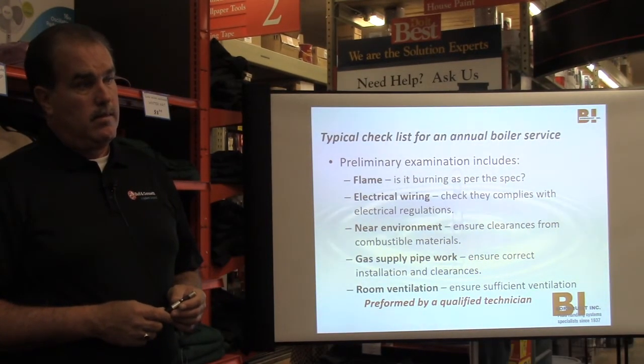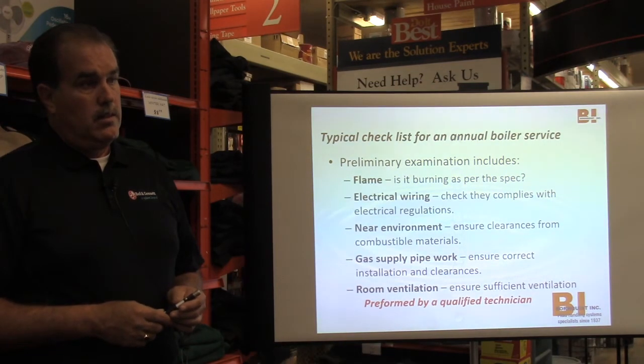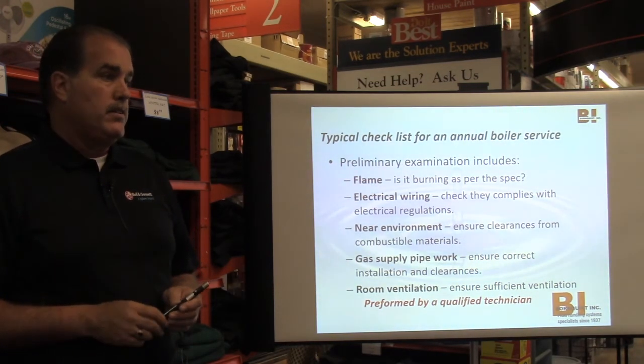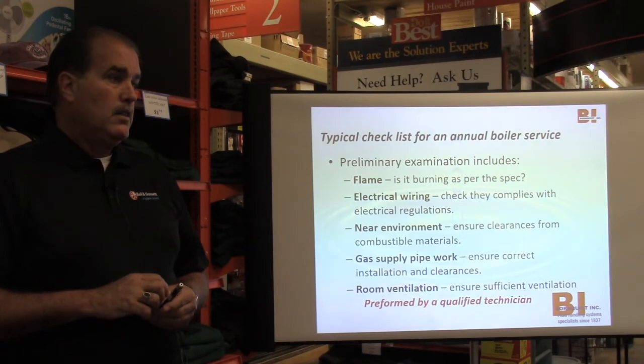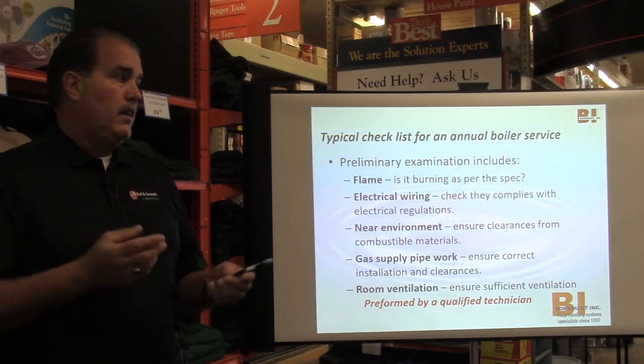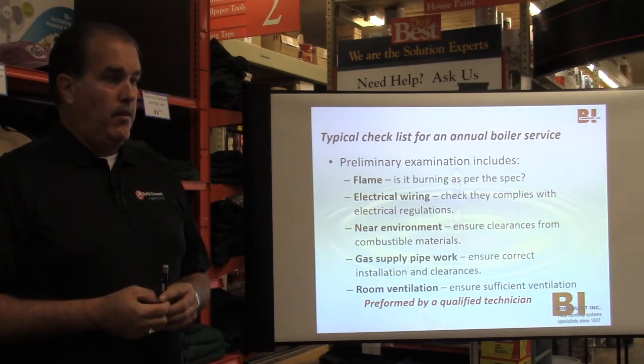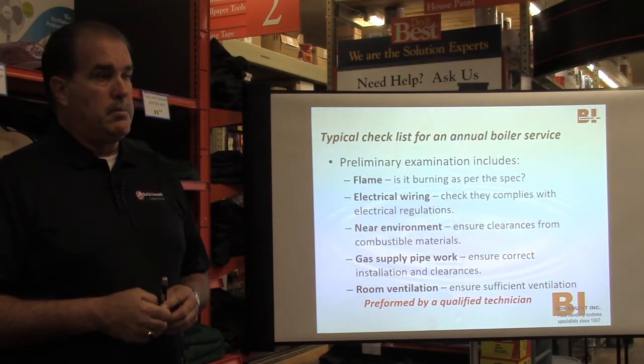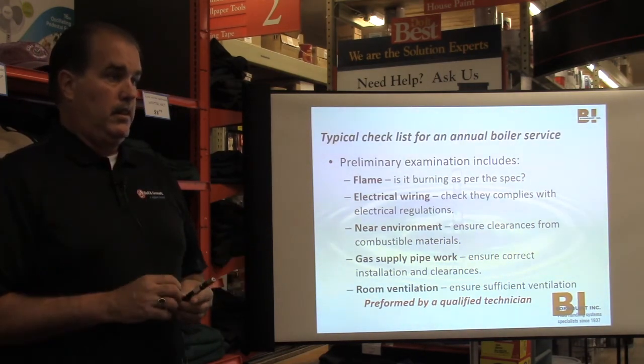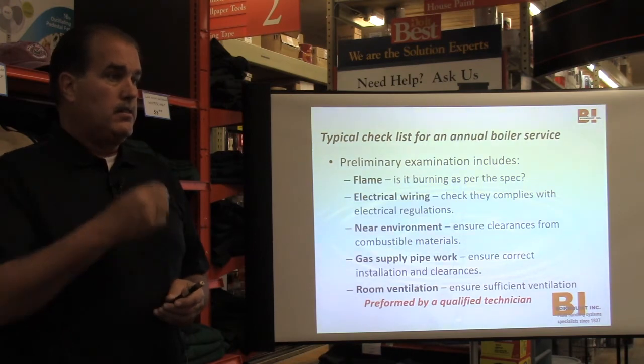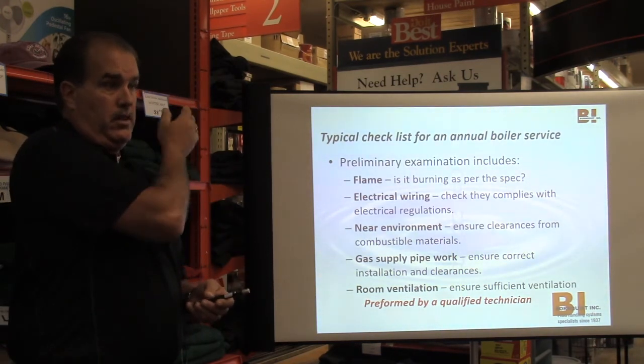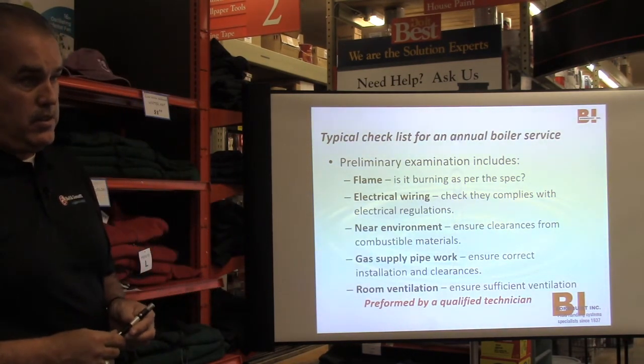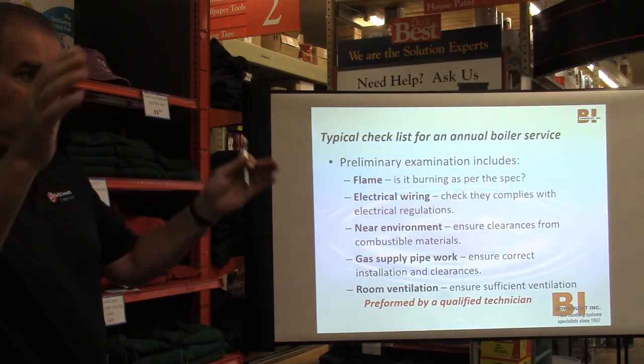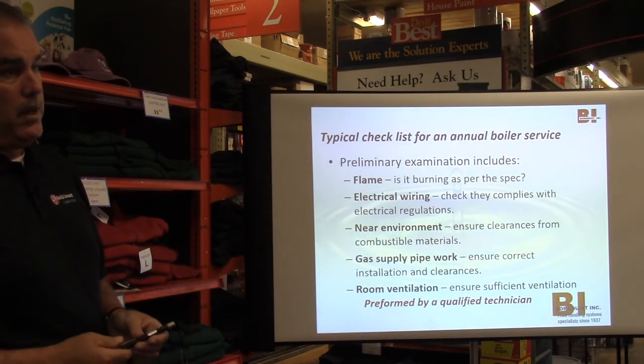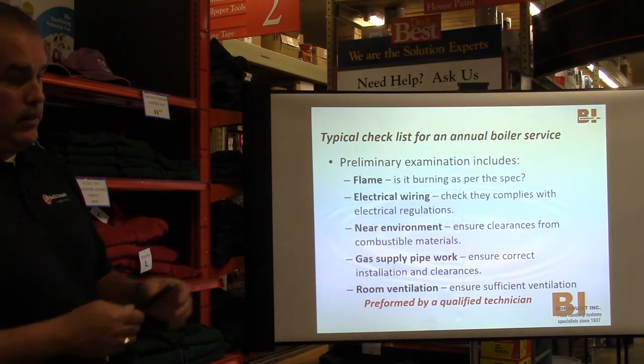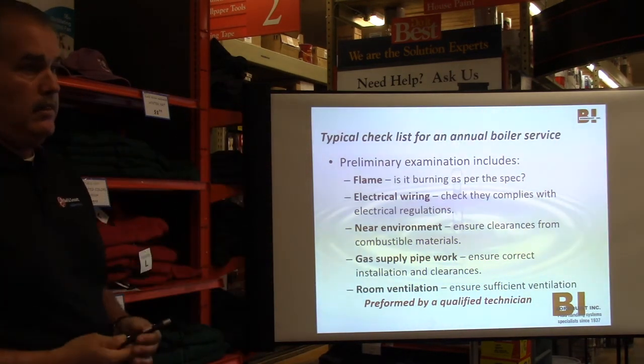If it's an atmospheric boiler, which we have, would you really recommend every year for that still? Yeah, we always recommend annual maintenance. It's always a good idea. I don't know what they charge around here, but it's not a huge expense, and at least you've had somebody look at that piece of equipment. Because if he's doing what he's supposed to be doing, he's looking at more than just your combustion. He's looking at the whole way it's installed. Because when I walk into a boiler room, I look at the boiler, but I'm looking around at everything.